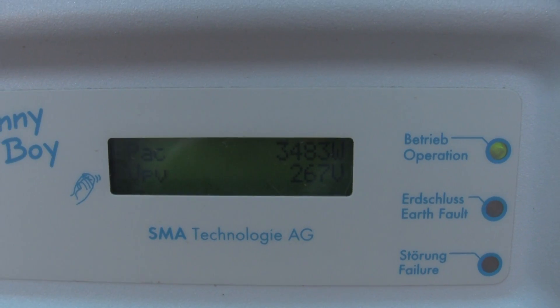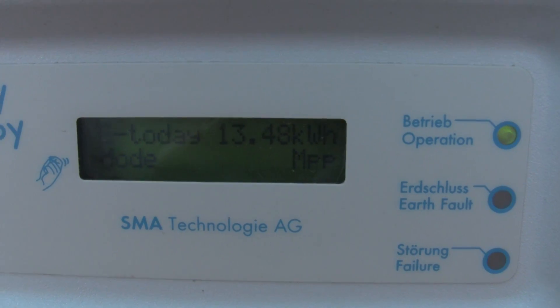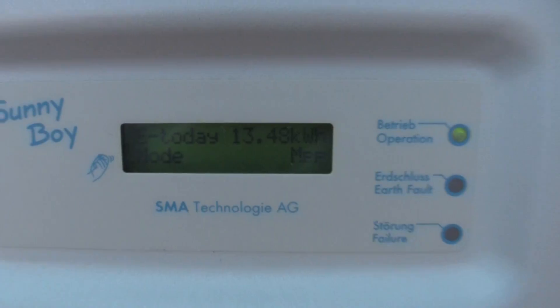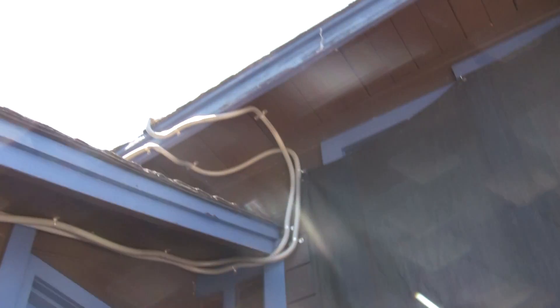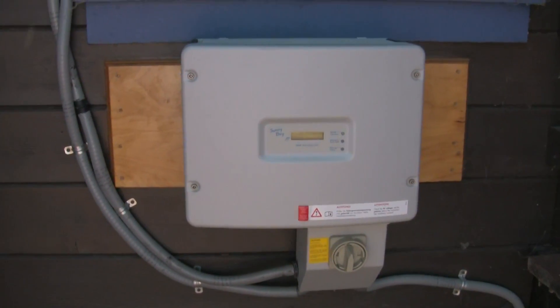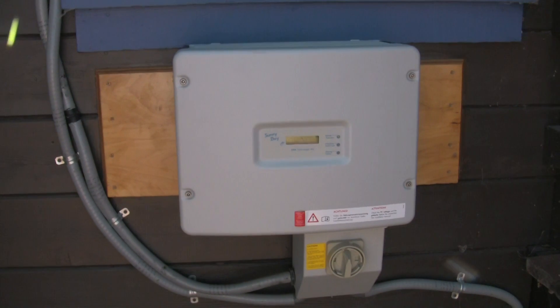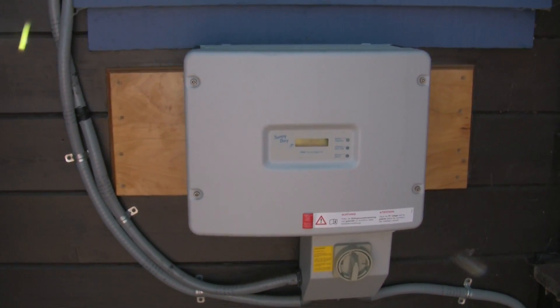We're reading 3,483 watts at 267 volts DC, and today we have made 13.48 kilowatt hours so far. I'm going to go up and do a monthly maintenance and a little cleaning on the array, and demonstrate just how much solar panels are derated by high temperatures.